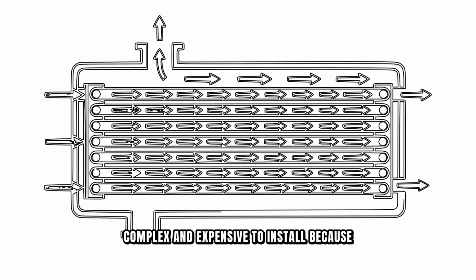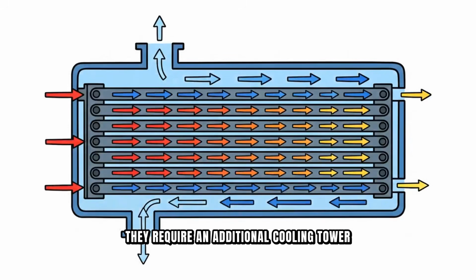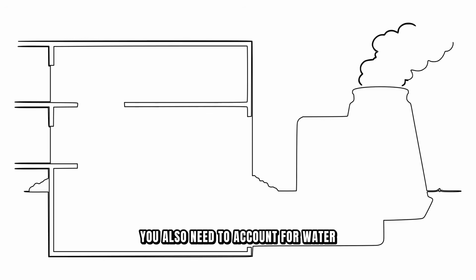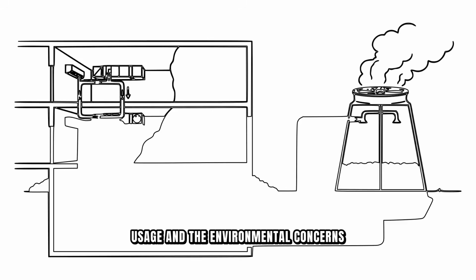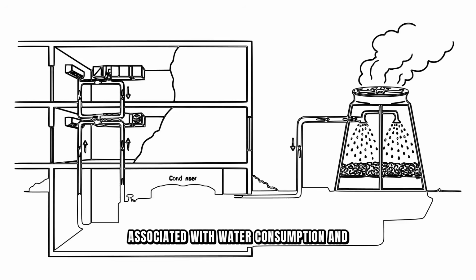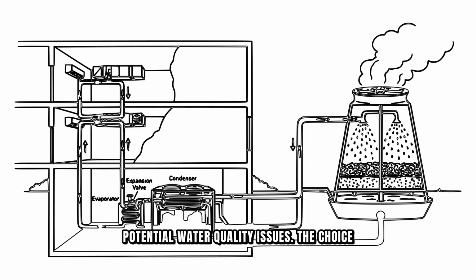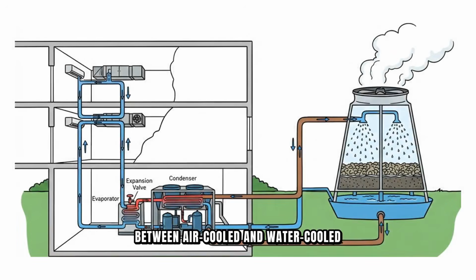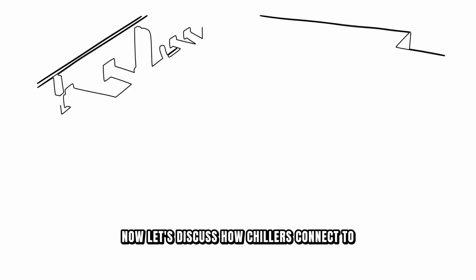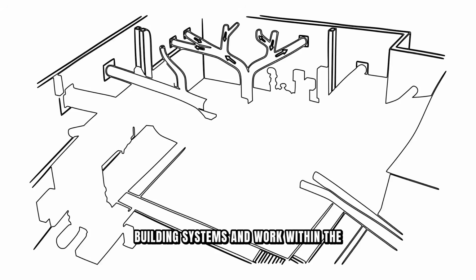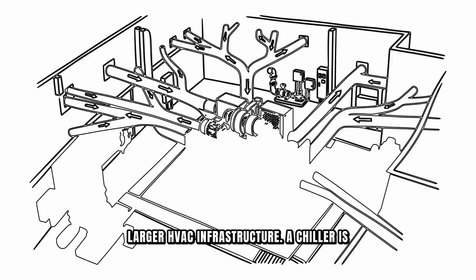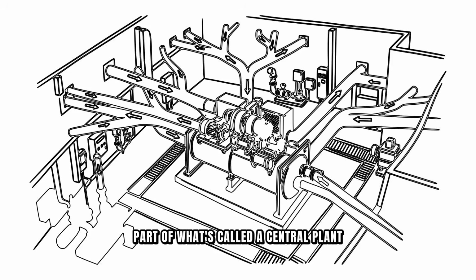They're more complex and expensive to install because they require an additional cooling tower and water treatment systems to prevent corrosion and biological growth. You also need to account for water usage and the environmental concerns associated with water consumption and potential water quality issues. The choice between air-cooled and water-cooled typically comes down to your climate, available space, budget, and local water availability and regulations. Now let's discuss how chillers connect to building systems and work within the larger HVAC infrastructure.